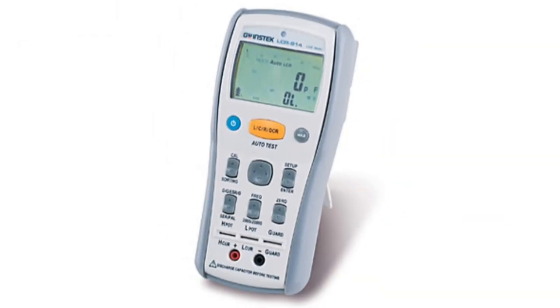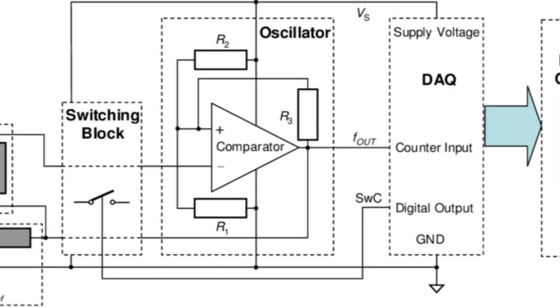The principle an LCR meter is based on is the measurement of impedance, a physical property representing the opposition to the flow of electrical current in a circuit. LCR meters work by measuring the current flowing through a device under test, the voltage across the device, and the phase angle between the measured voltage and current. By analyzing these parameters, LCR meters can accurately determine the inductance (L), capacitance (C), and resistance (R) of electronic components.